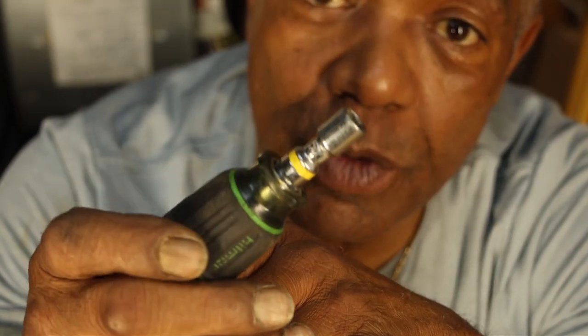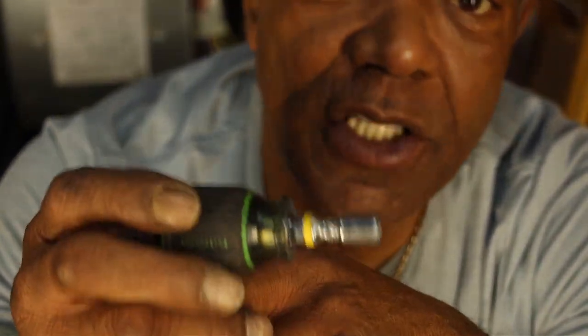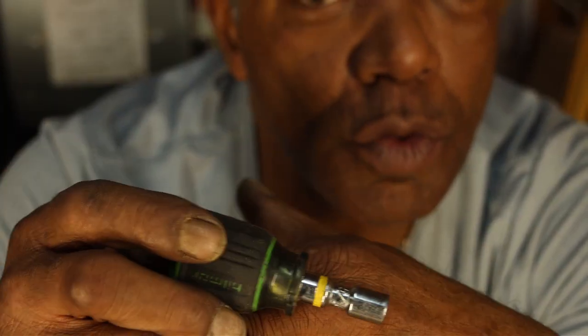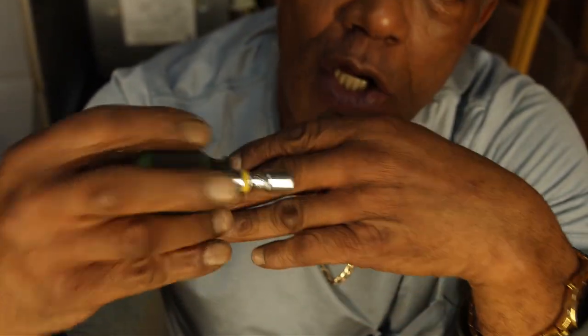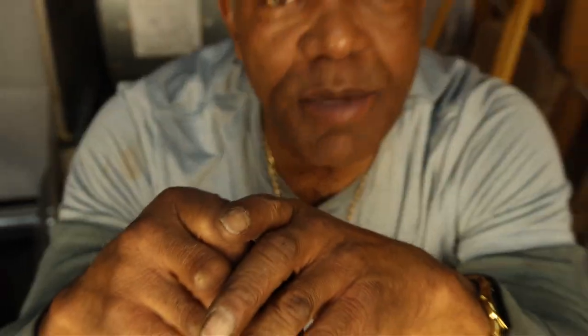These are must-have tools. A lot of the nuts that we need to remove in order to replace flame sensors, glow plugs, pressure switches, flame rollout switches, limit switches. Sometimes they're in very awkward positions, and we have to figure out a way to get them out so that we can do our job. Well, throughout the class, we're going to remove some of those flame sensors. We're going to remove flame rollout switches. We're going to remove glow plugs, and I'll show you how to put them back, and I'll show you how to use these tools, okay?